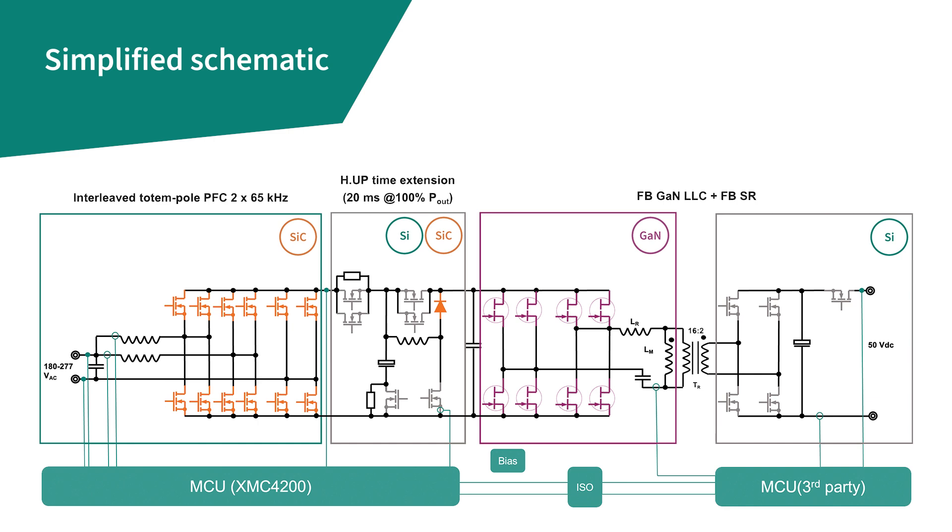This stage rectifies the AC input to 405 volts DC and provides power factor correction functionality and current total harmonic distortion or ITHD functionalities. The second DC-DC conversion stage is a full-bridge primary, full-bridge secondary, resonant LLC DC-DC converter.